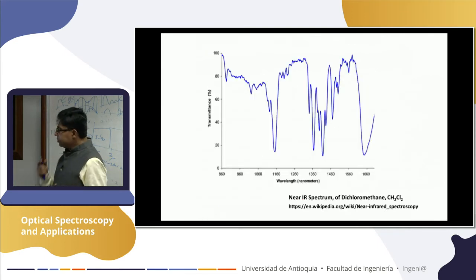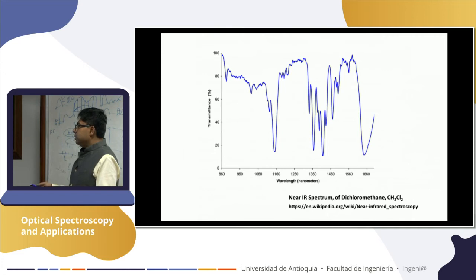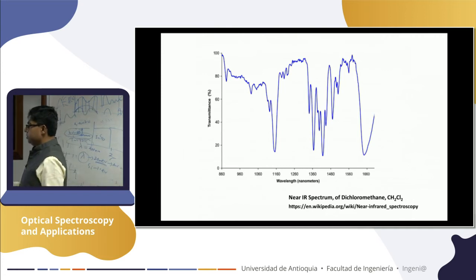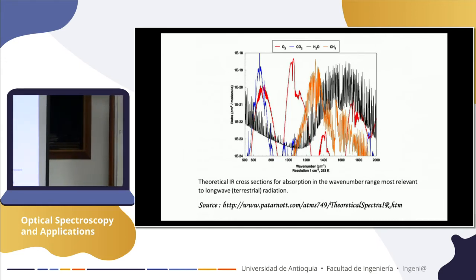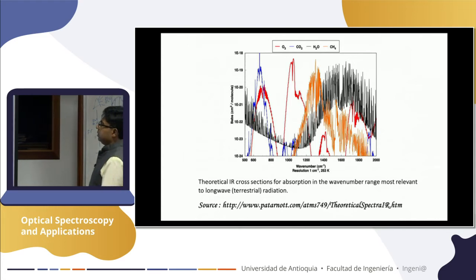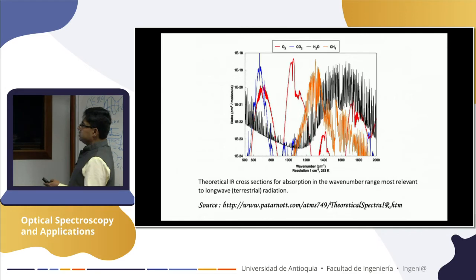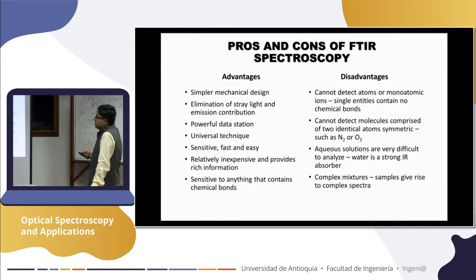Just to give a real-life example: measuring gases like ozone, CO₂, water, methane — all have very distinct absorption peaks as a function of wavelength. As soon as you match the spectrum you can identify the molecule. FTIR advantages over a normal spectrometer include: simple mechanical design, no dispersion needed, no moving slit, high precision wavelength measurement, faster measurement, and no stray light problems that you'd have with a grating or prism-based spectrometer.